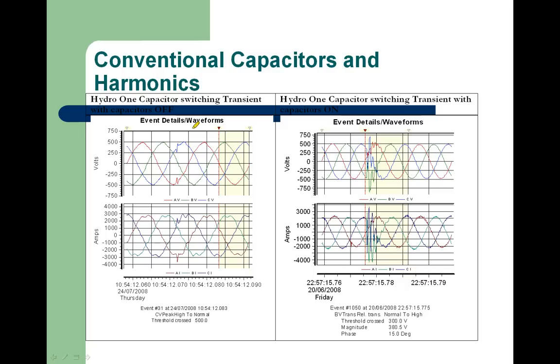This particular one is a small one. You can see a switching. There's a zero drop. The voltage in here drops as the capacitance is switched on. Now, this would be typically what you would see in a facility if you either did not have any capacitors or if you had a harmonically filtered capacitor bank. One of the problems that we see with conventional capacitors is the utility switching capacitors sometimes will resonate or interact with capacitors in facilities.